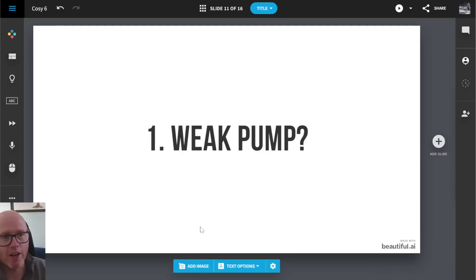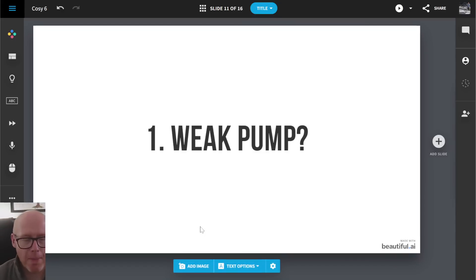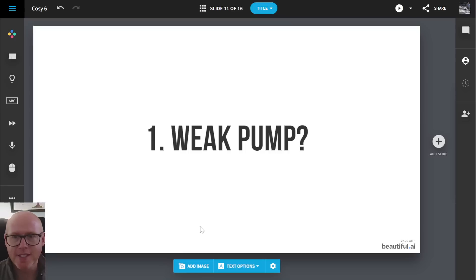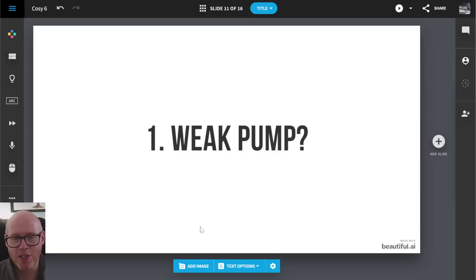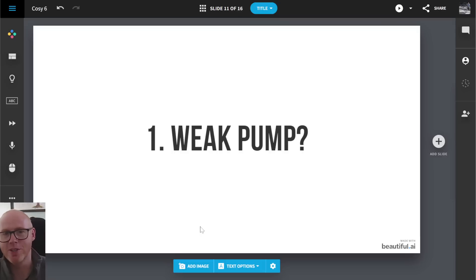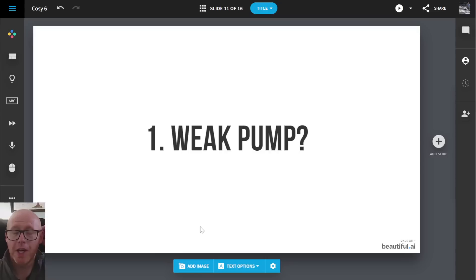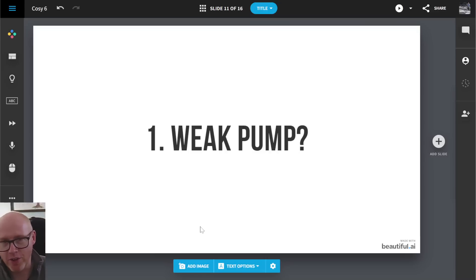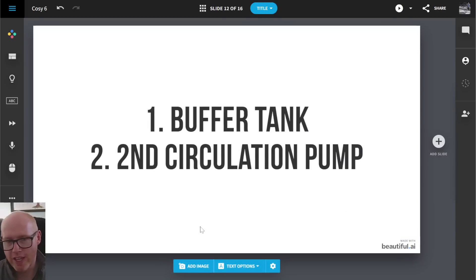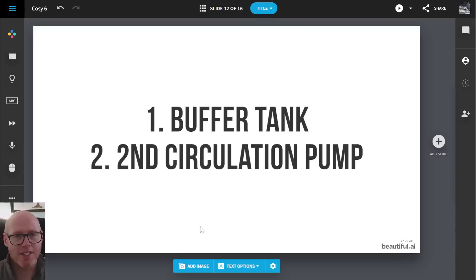But it's still possible to calculate all of these things. So has the Cosy 6 got a weak pump? Probably not. This is probably an extreme case. But clearly Octopus Energy know the specifications of the pump. They know how many meters head. They could easily do the calculations. I mean, even an enthusiast like me, I can easily do the calculations for the external pipes, which I presume will run in 28 mil. Well, copper pipe, the internal pipe work, you'd have to do a little bit of guesstimation. But if they've taken apart a bit of the house, then they could probably do some good calculations.